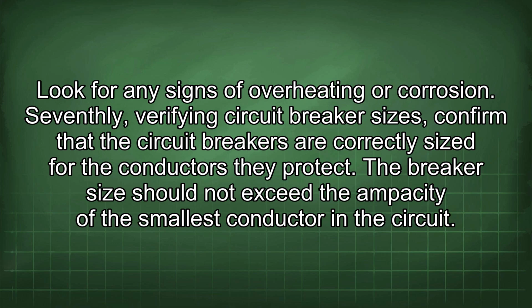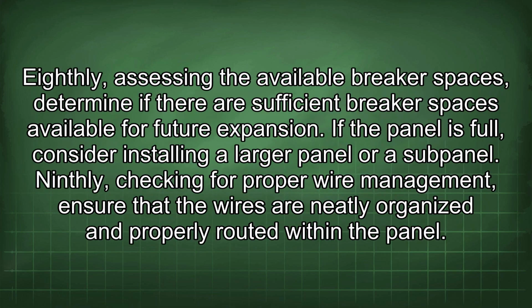Seventhly, verifying circuit breaker sizes. Confirm that the circuit breakers are correctly sized for the conductors they protect. The breaker size should not exceed the ampacity of the smallest conductor in the circuit. Eighthly, assessing the available breaker spaces. Determine if there are sufficient breaker spaces available for future expansion. If the panel is full, consider installing a larger panel or a sub-panel.